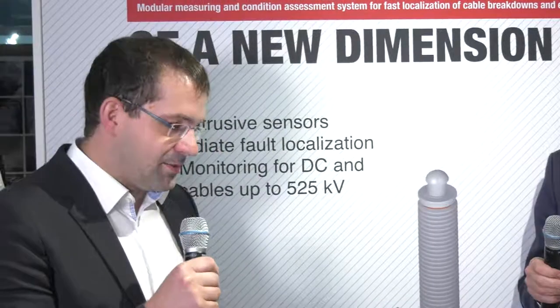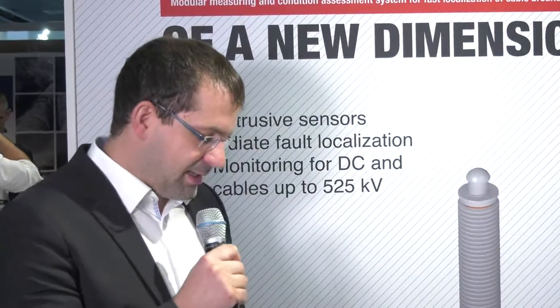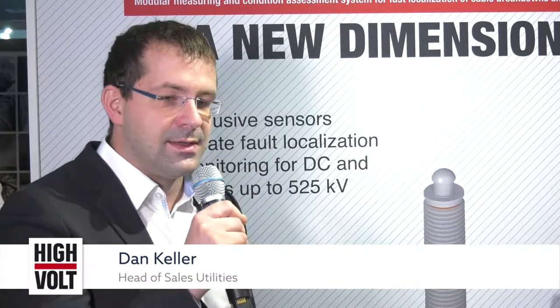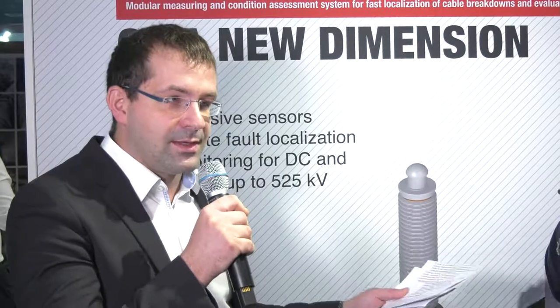I think from the engineering point of view, very interesting development. Just to get an idea what is possible to test, how it is possible to test the cables. With the six reactors in parallel, at a voltage of 260 kilovolt, it's possible to test such cable length of 150 kilometers.